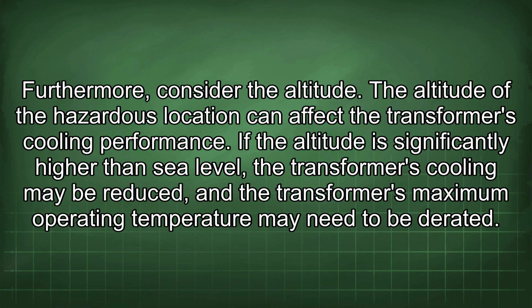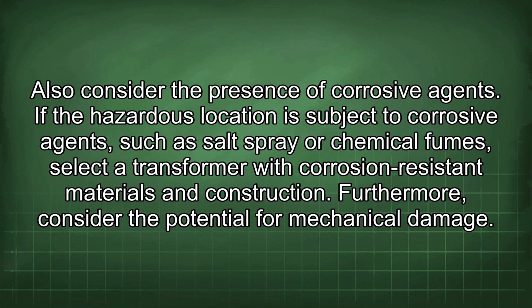Furthermore, consider the altitude. The altitude of the hazardous location can affect the transformer's cooling performance. If the altitude is significantly higher than sea level, the transformer's cooling may be reduced, and the transformer's maximum operating temperature may need to be derated. Also consider the presence of corrosive agents. If the hazardous location is subject to corrosive agents, such as salt spray or chemical fumes, select a transformer with corrosion-resistant materials and construction. Furthermore, consider the potential for mechanical damage.